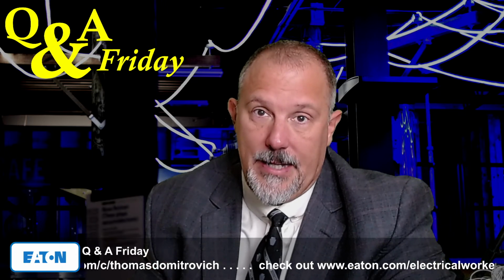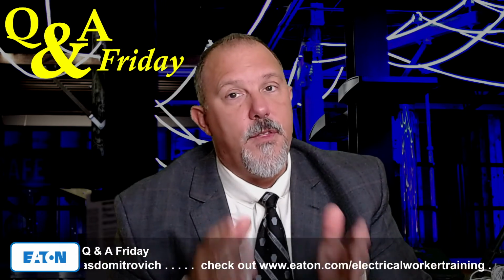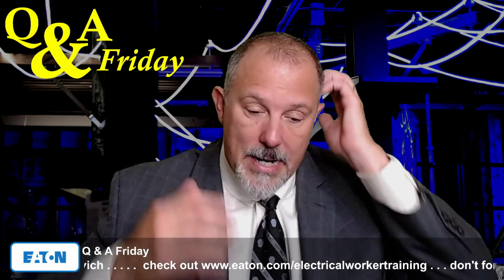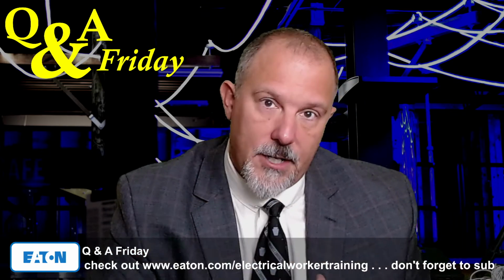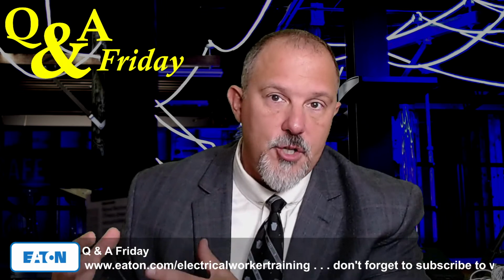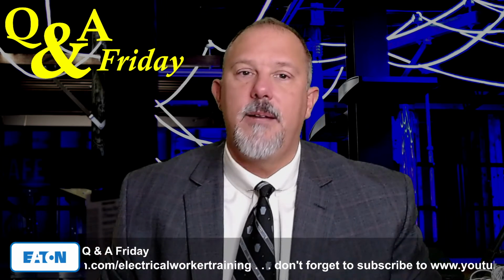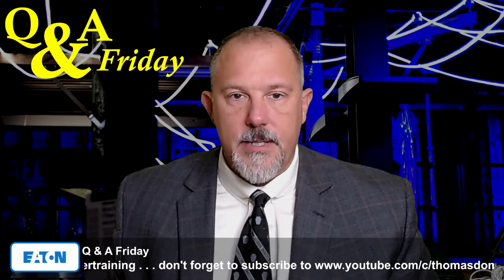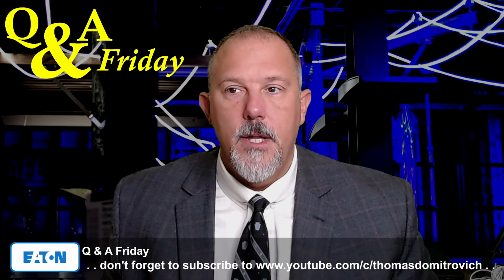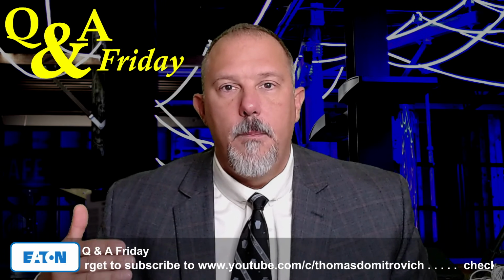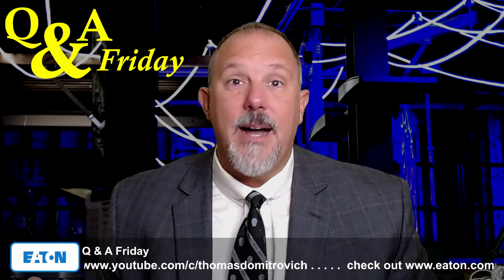Depending upon where my arcing current is, now remember the time current characteristic curve, when I talk about incident energy reduction due to an upstream overcurrent device, I'm not talking about comparing the bolted fault current with the clearing time. Hey, Robert, good to see you too, brother. I'm not talking about the bolted fault current clearing time with the upstream overcurrent device. I'm talking about the arcing current. And the arcing current is going to be a lower value of current.